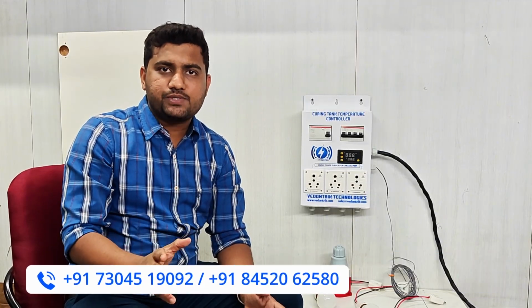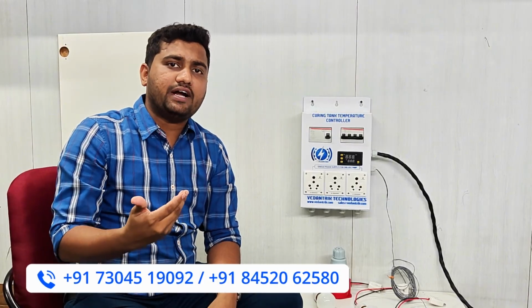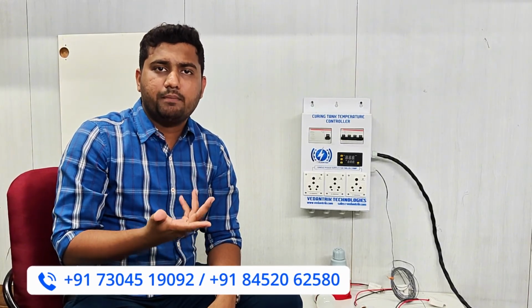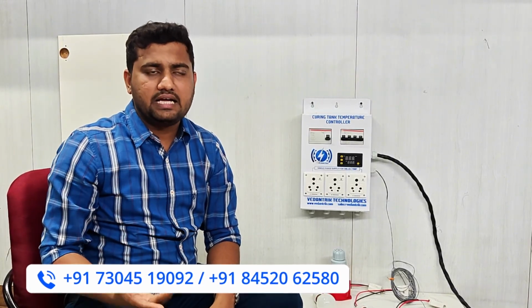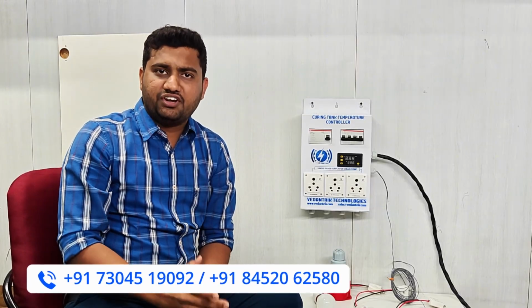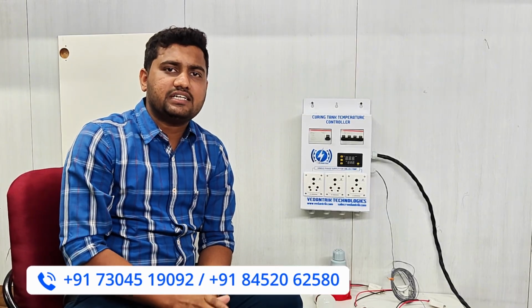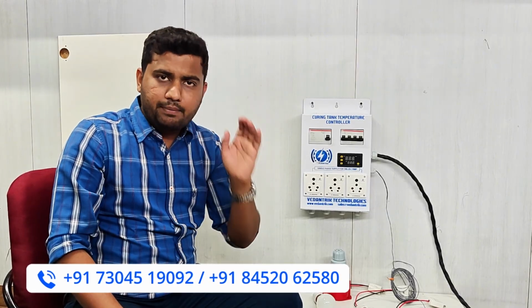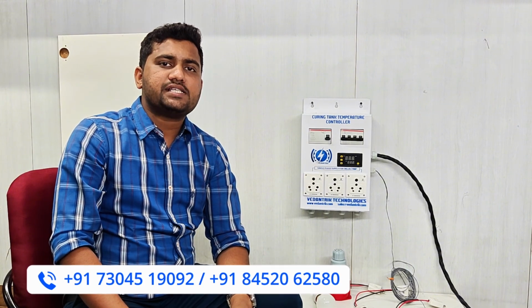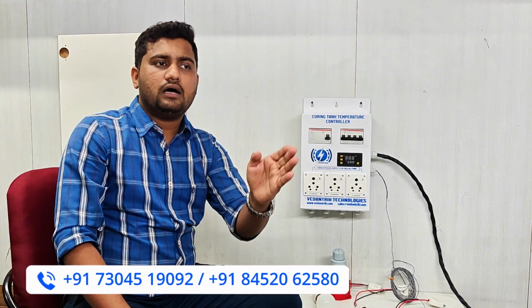www.vedantrik.com. So you can visit our website. On that we have given a very clear cut formula by which you can find out how many heaters you can buy. But for a thumb rule, I will explain that we provide a 4 kilowatt 3-phase heater. So 4 kilowatt 3-phase heater is very much capable to maintain the temperature of 27 plus minus 2 for at least 3000 liter capacity tank.